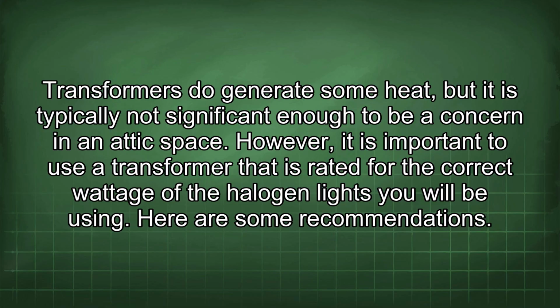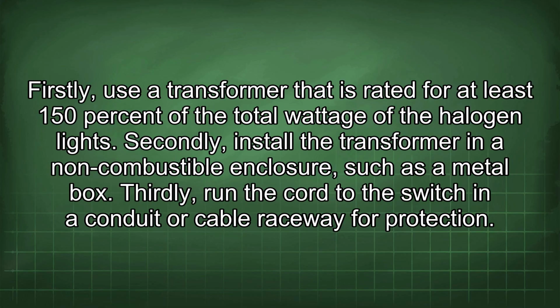However, it is important to use a transformer that is rated for the correct wattage of the halogen lights you will be using. Here are some recommendations. Firstly, use a transformer that is rated for at least 150% of the total wattage of the halogen lights. Secondly, install the transformer in a non-combustible enclosure such as a metal box.